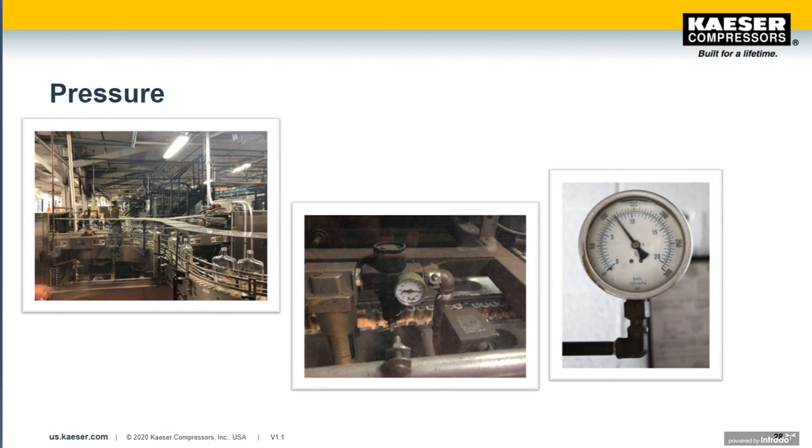The important things to note: high and low values on either one, and the timing. Look for any rapid changes, where they are located within the system, and know their limitations in terms of accuracy, 2 versus 4 inch gauges, and the fact that probably none of them are calibrated at all.